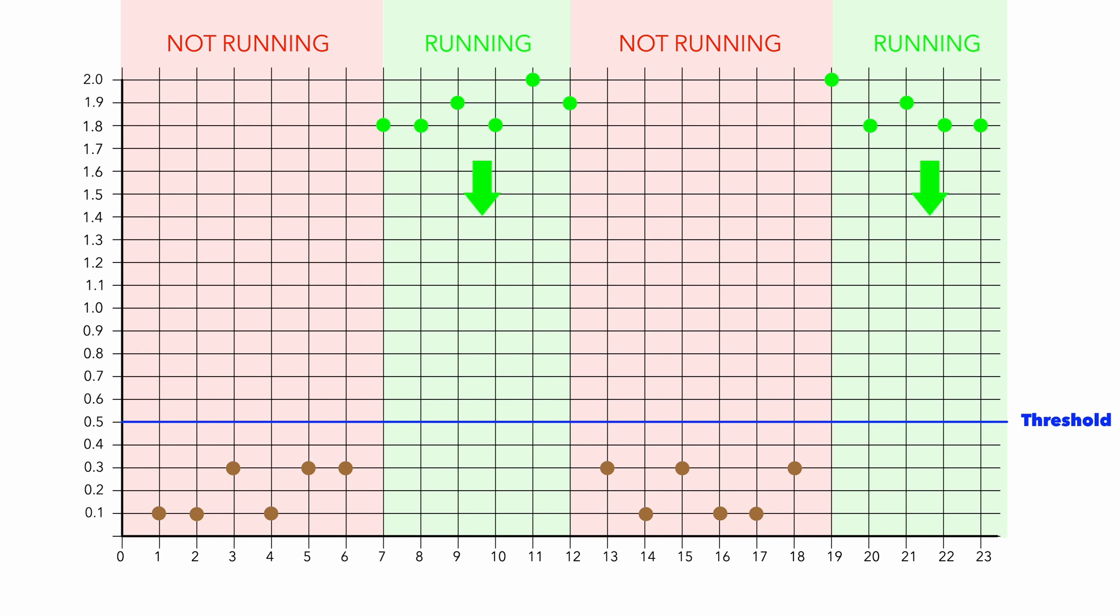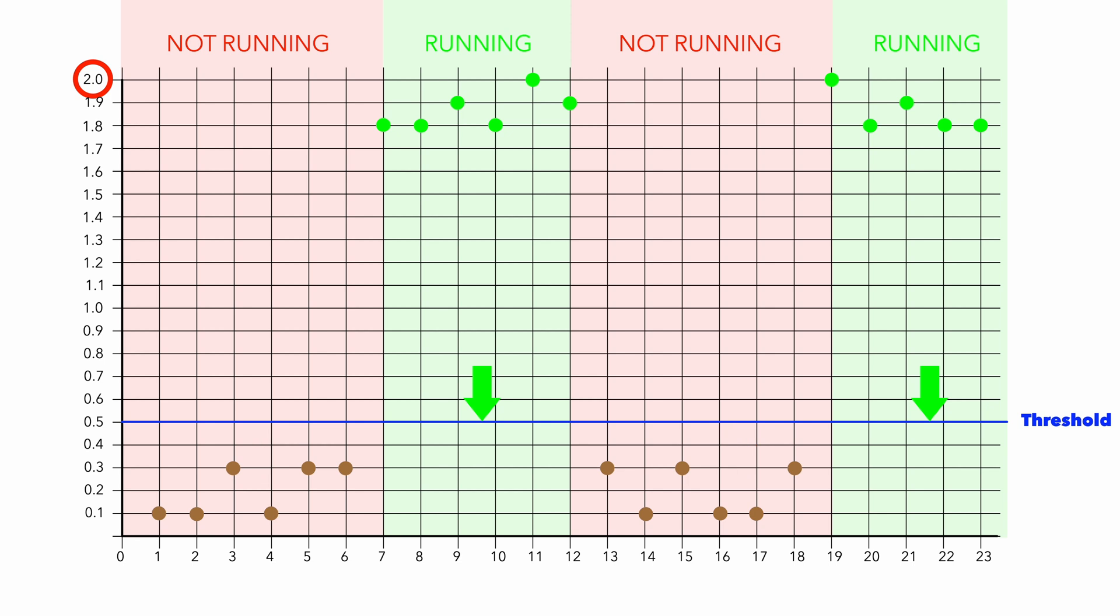Threshold value has to be lower than normal machine vibrations and higher than noise values. It means if normal machine vibration is around 2 mm per second and noise value is around 0.2 mm per second, then the threshold value should be set, for example, to 0.5 mm per second.